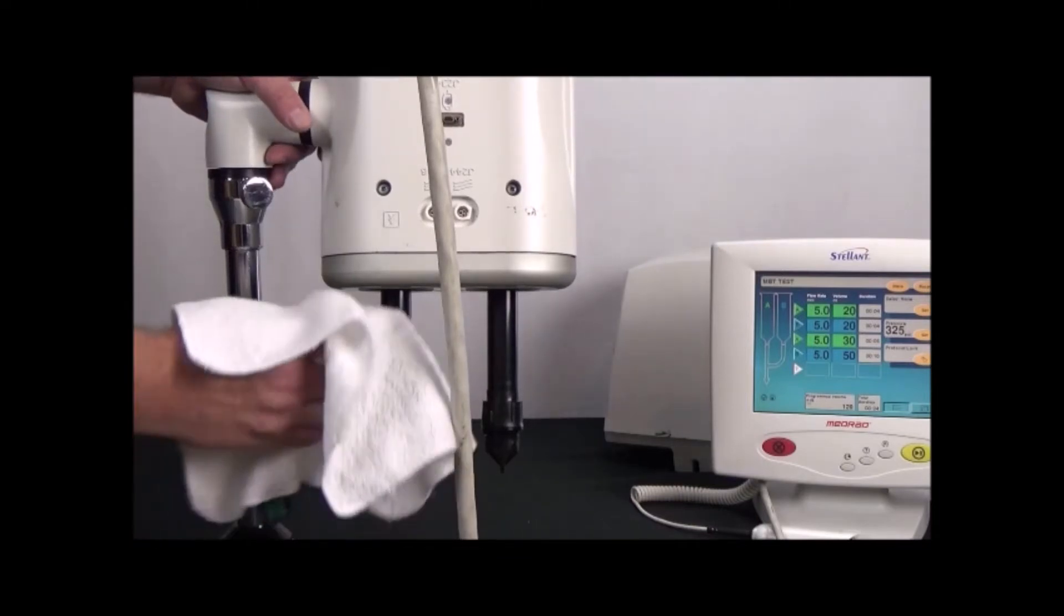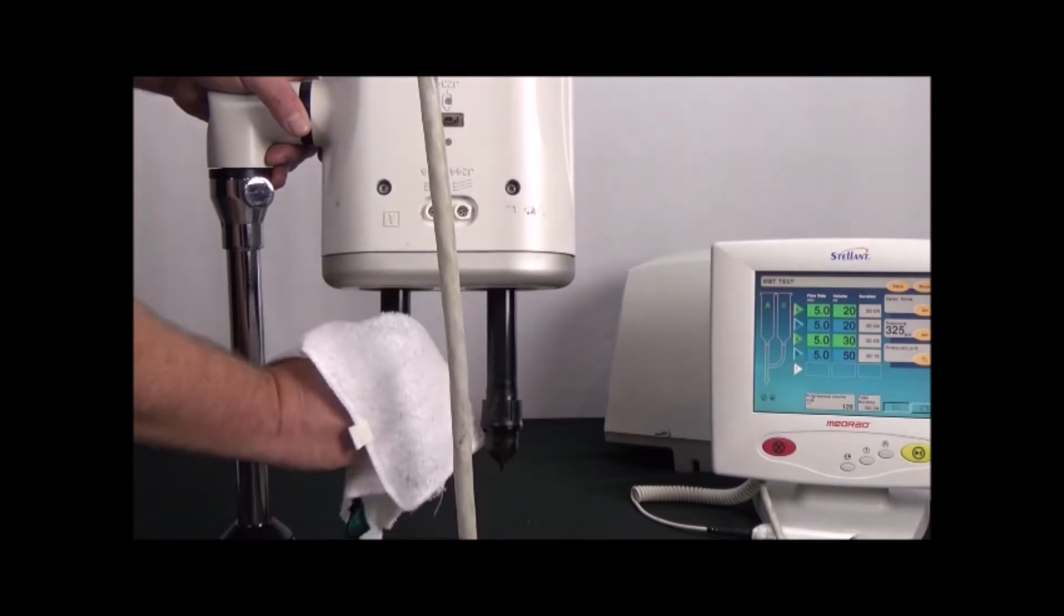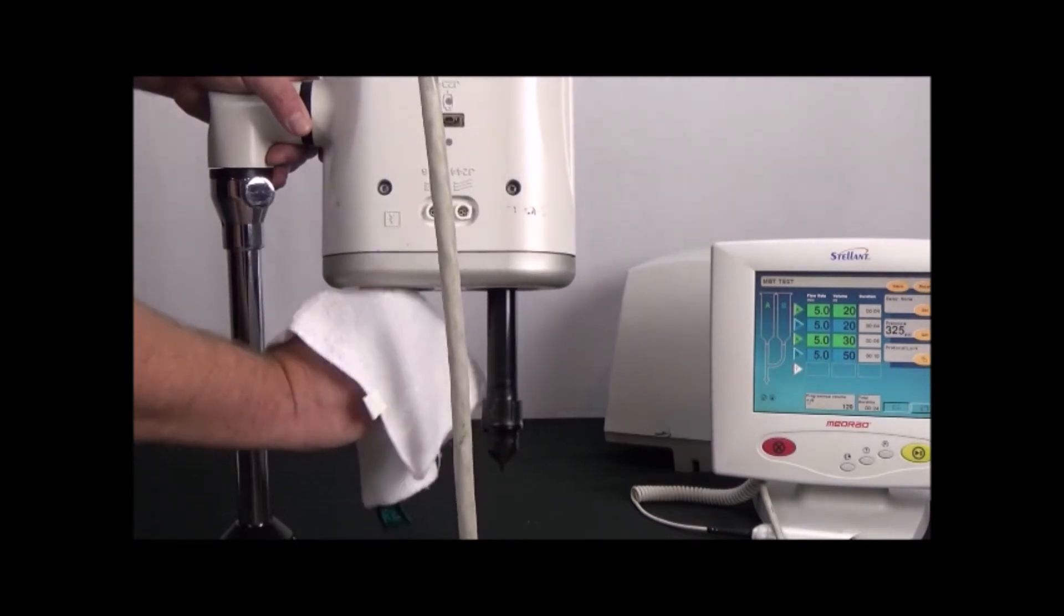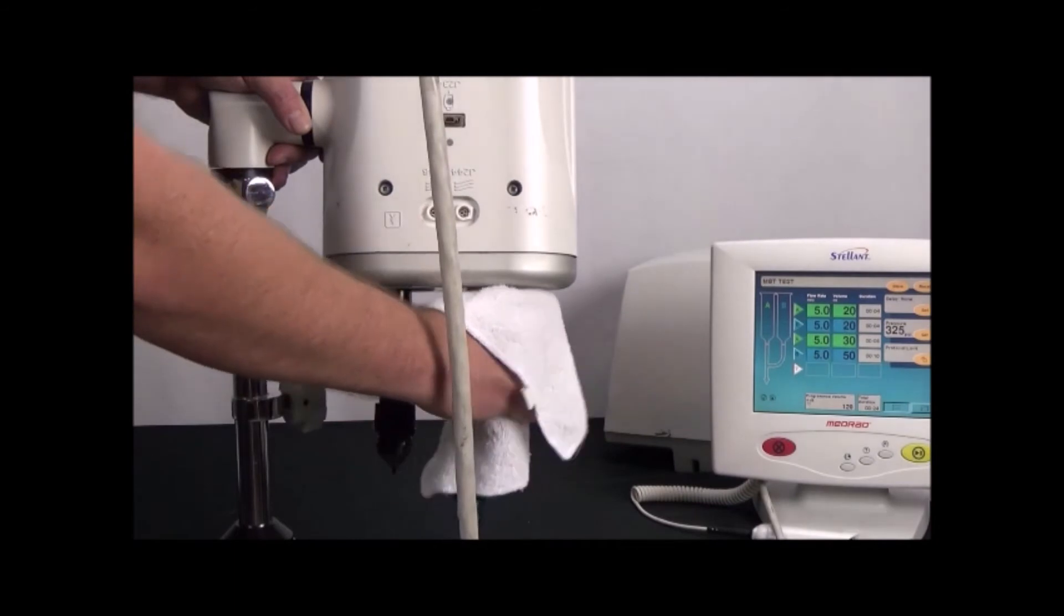With a very damp cloth, clean both pistons of any dried contrast or saline. When doing this, be sure to leave some moisture on the pistons.